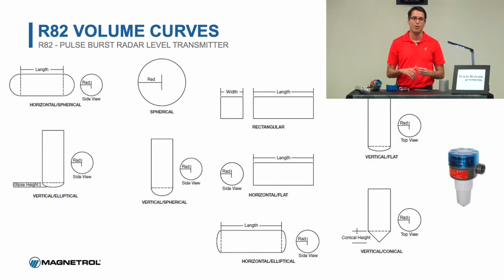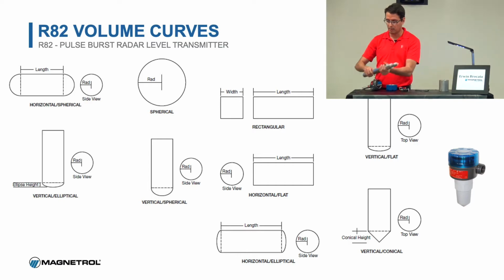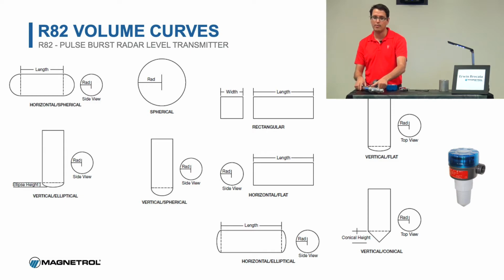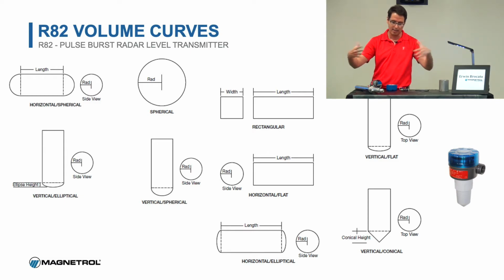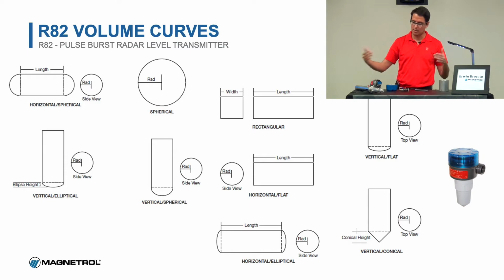All that stuff we need to know because it will matter, because unlike the guided wave radar where you have your conductor, and your electromagnetic signal travels through the conductor, with the non-contact radar, it's going through air. So anything around that beam might hit that beam and reflect back and be detected as an echo. Now we can eliminate those false echoes, as we call them, through the software. It can be done, but it takes a little bit of time to set that up. So in conclusion for this particular slide, we need to know the dimensions of the tank and if there's anything inside of the tank that could be in the way.